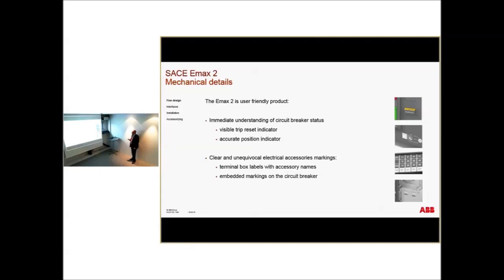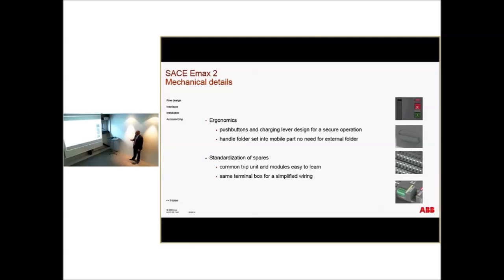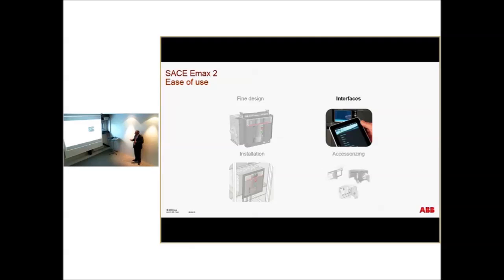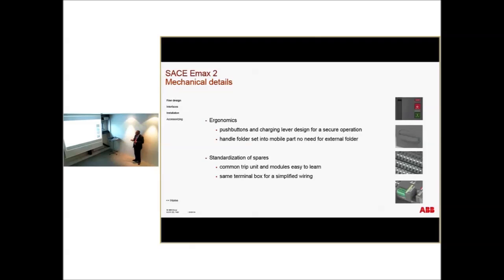The labeling is not just the connection numbers on top, 21, 22, 23, but also what is an auxiliary contact, what is an opening coil. And you have an indication on the bottom, something that is not rocket science, but is an improvement. And then you can read inside what the coil is. The racking handle, you will see later downstairs. Basically, it's fitted in the front. This is an improvement that I showed you already before.